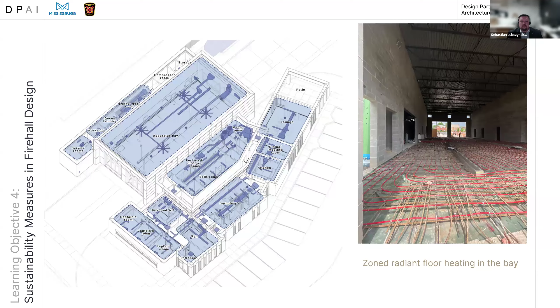In the apparatus bays, heating is provided primarily by in-floor radiant heat, delivering steady, durable warmth in a large, high-volume space. Unit heaters are then located at each bay door and controlled by localized sensors to activate only when the temperatures drop, typically when the doors open in the winter, allowing for targeted recovery without running continuously. Importantly, all of these systems are integrated into the building automation system and are monitored by the city's building management team. This allows for real-time oversight, performance optimization, and long-term operational control.